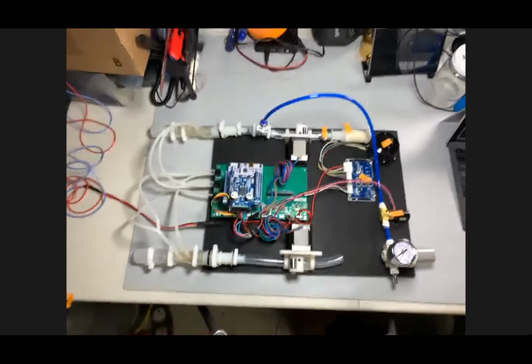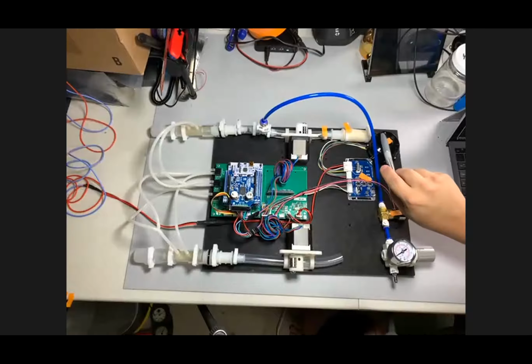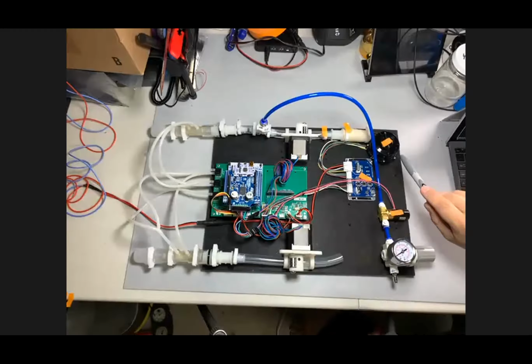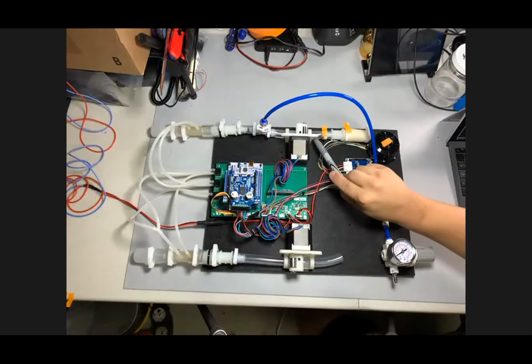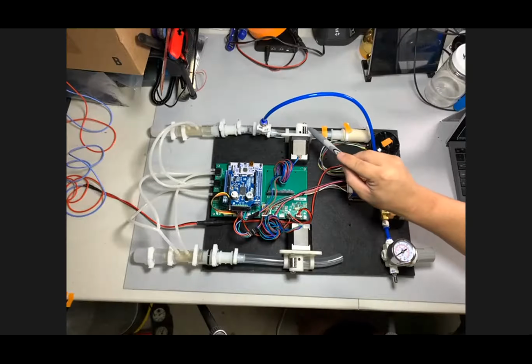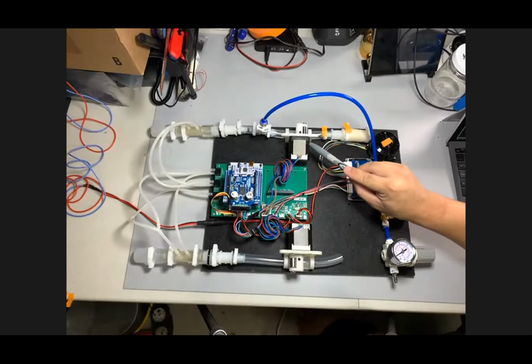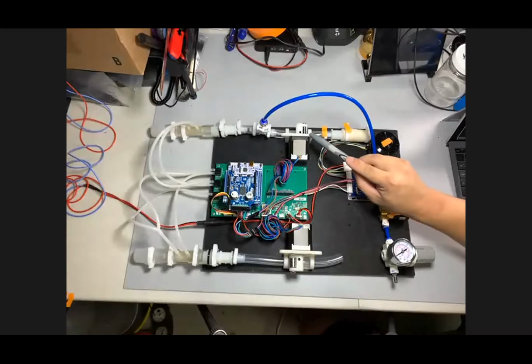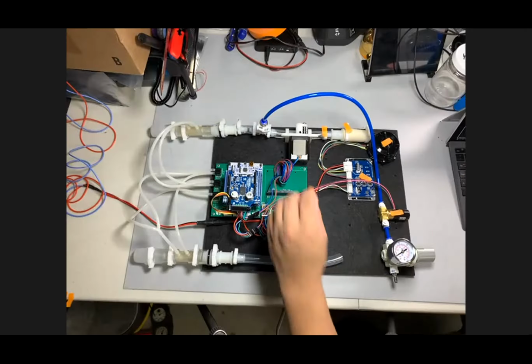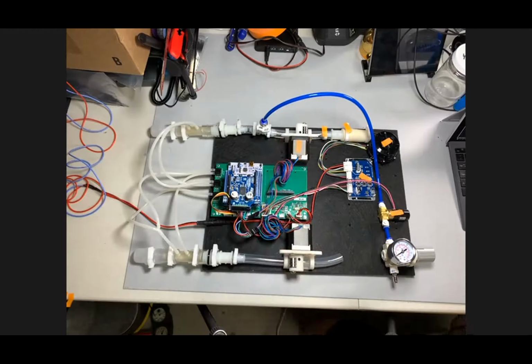The pinch valve provides a proportional control for the blower. The inertia of the blower and the time it takes for the blower to spin up and spin down is longer than the fastest breath that we expect to be generating from the ventilator. So in order to get the response time that we need, we need something that can move faster than the blower can change speed. So downstream from the blower, this pinch valve serves that purpose. It's driven by these commonly available stepper motors. You can find these all over the world. The 3D printed part here is a custom part. It can also be injection molded or machined. For the time being, this has worked really well, and we're going to go ahead and go with that for the demo.